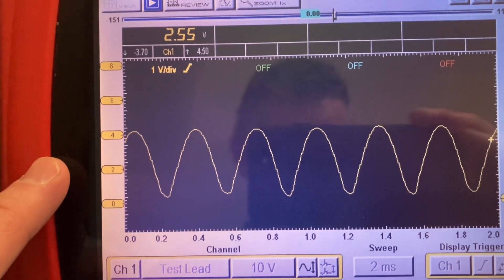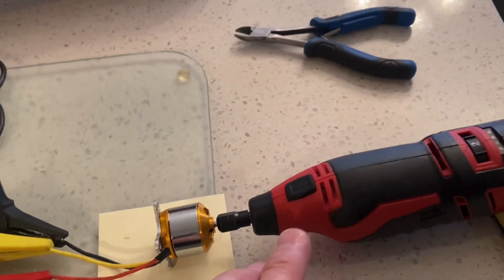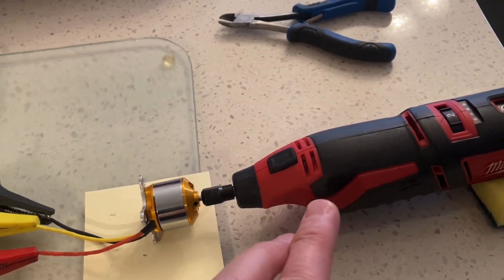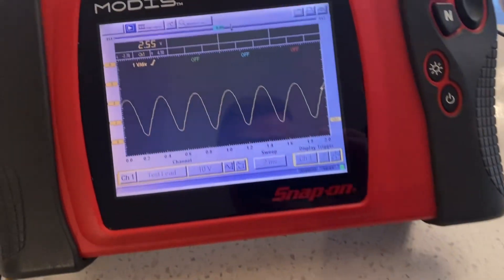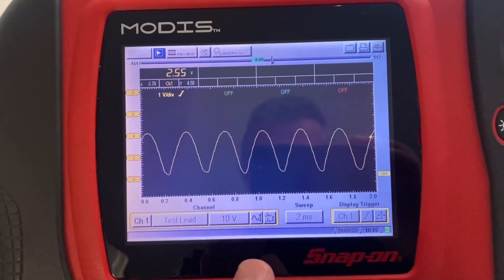I don't think you'd be operating very long with a shorted diode. You can hear the massive load that was being imposed on the system because of course with the short, some of the current is running back through the windings when it shouldn't be, so it was loading the system up.